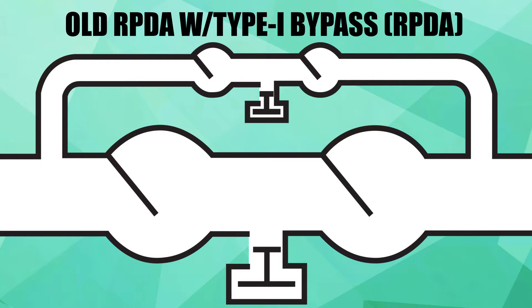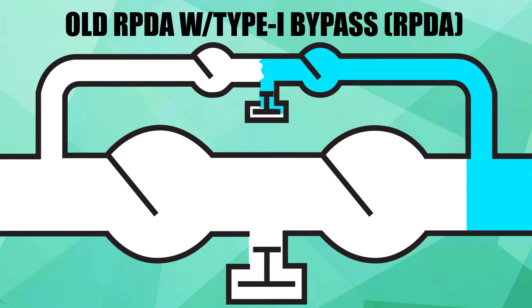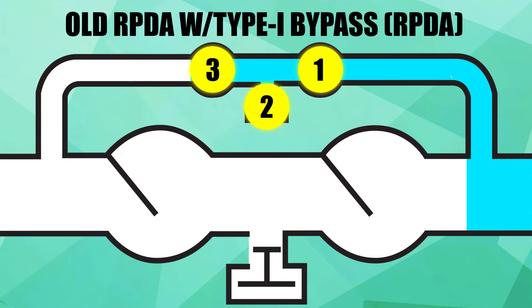Now, a comparison of the paths through the bypass. During a backflow condition on an old RPDA with a Type 1 bypass, the water first encounters the bypass second check. Next, the water encounters the bypass relief valve. And then the water encounters the bypass first check. This provides three mechanisms of backflow protection.